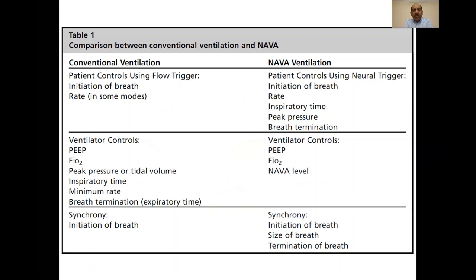Comparing conventional ventilation with NAVA ventilation, the key differences are highlighted in this table. In conventional ventilation, patient flow is the main trigger. In NAVA ventilation, it is the neural signal — the electrical activity of the diaphragm. Because of this, in conventional ventilation only initiation of breath is synchronized, while in NAVA ventilation the initiation of breath, the size of the breath, and the termination of the breath are all three synchronized.